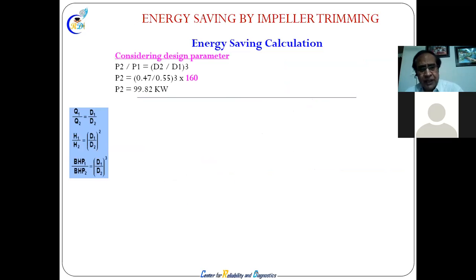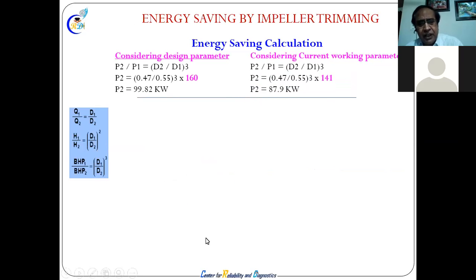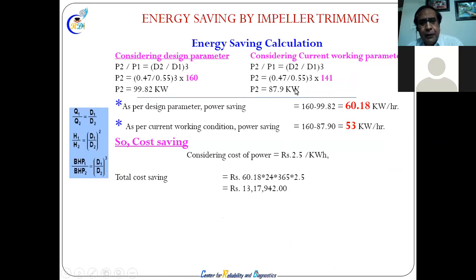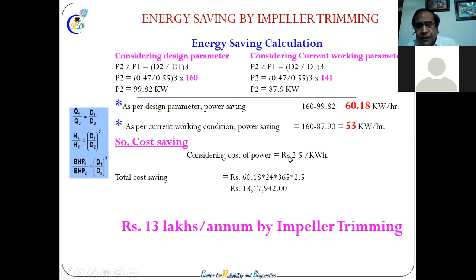Okay, so for the energy saving in that process, the initial design was this, the current working parameter is this, and in the current working parameter they are already getting less kilowatt, because it was 141 kilowatt and here it is 99.8 kilowatt, and the current working pressure is this. As per the current working condition, the power saving they are getting is 53, but here they have done it by changing the impeller diameter to 470, and they got a saving of around 2.5. The unit rate is 2.5, and they get a total cost saving of 13 lakhs per annum. It is running, they are getting 13 lakhs every year, because if they had run it at the original diameter, they would have lost this. Okay, this is a refinery case. I cannot tell the company name or details.